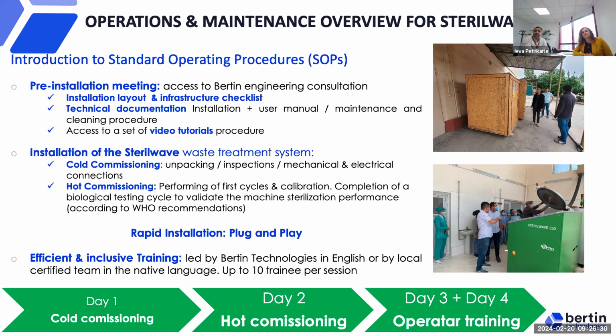Then comes the installation of the SteriLwave device. The installation basically takes 1 to 2 days, including the cold and hot commissioning. The cold commissioning is the unpacking, the inspection, and everything related to the mechanical and electrical connection of the machine. If everything is set up and checked prior to the arrival of the machine, this step should take less than 1 day.